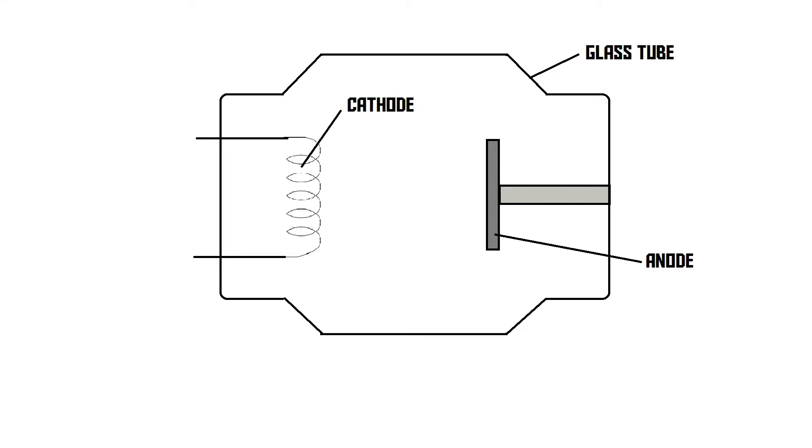Inside this tube, there is something called a cathode and something called an anode. When the X-ray machine is turned on, the anode becomes positively charged, meaning there's a lack of electrons inside that anode. The cathode is connected to a low voltage power supply. This cathode then heats up, just like the filament of a light bulb, and starts to glow.